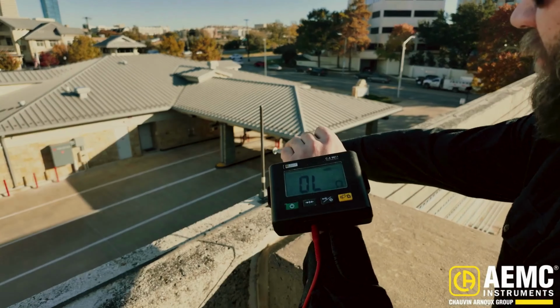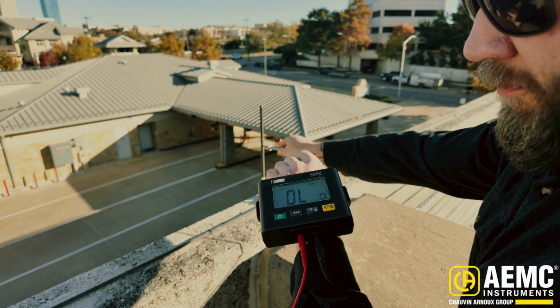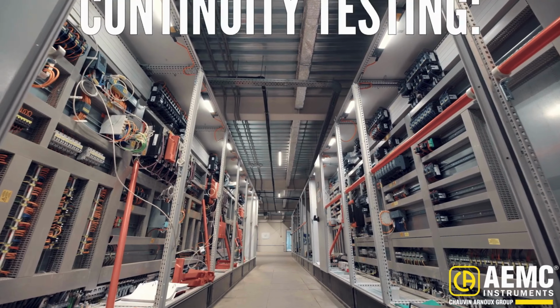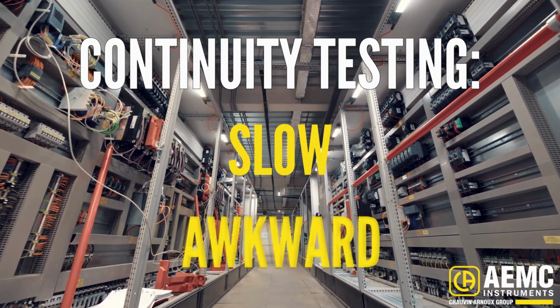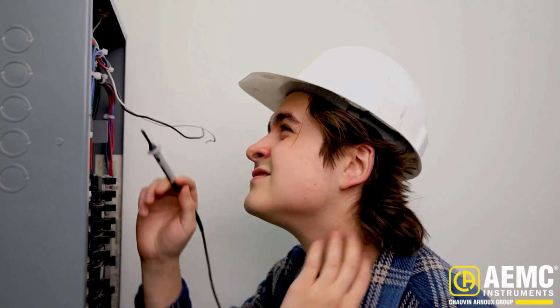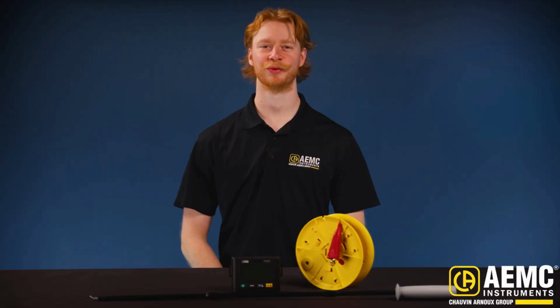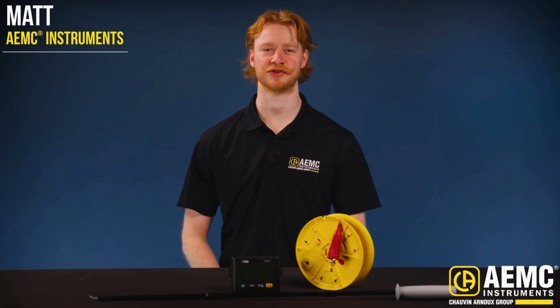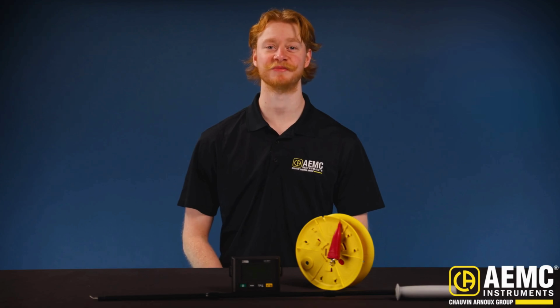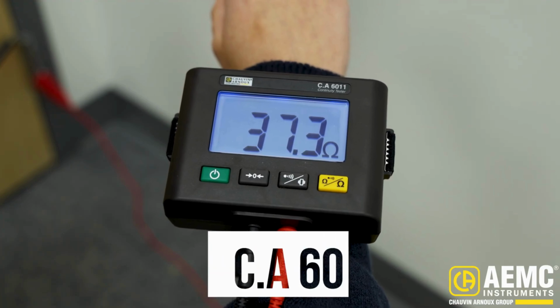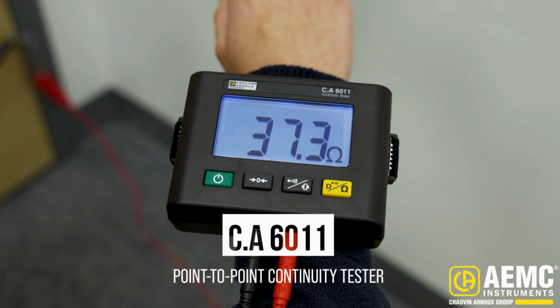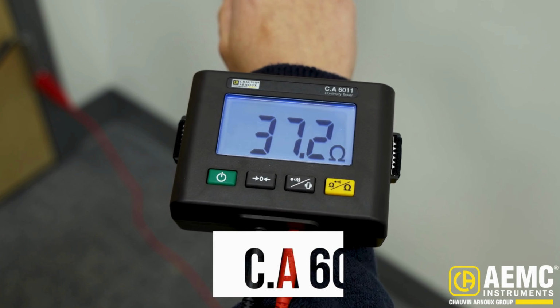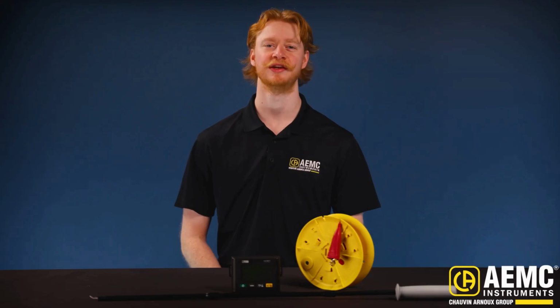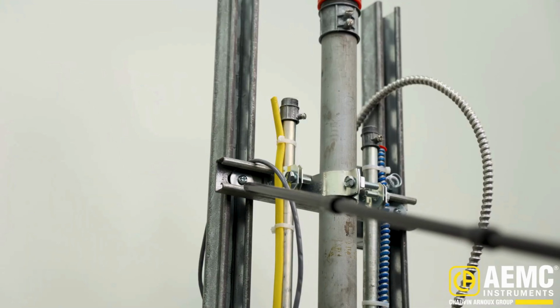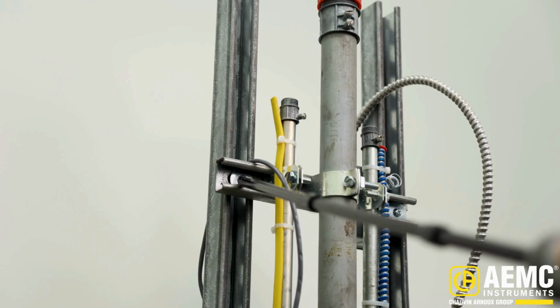If you've ever tested a large lightning protection system or chased equipment grounds around a big facility, you know continuity testing can be slow, awkward, and honestly a pain in the neck, literally. Today, we're introducing the point-to-point continuity tester model CA6011 from AEMC Instruments, a unique, wrist-worn test instrument that's lightweight, fast, and simple for verifying grounded pathways and connections over long distances, even in hard-to-reach locations, so you don't have to worry about that unnecessary strain.